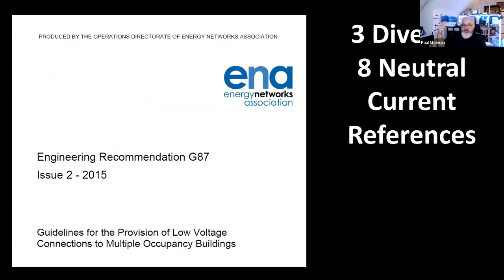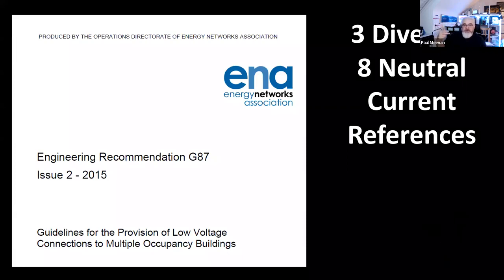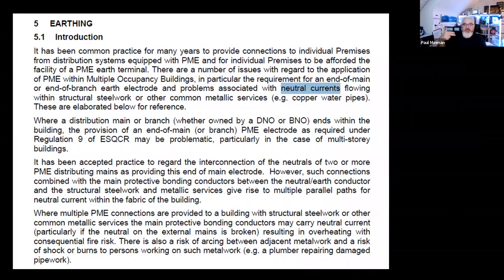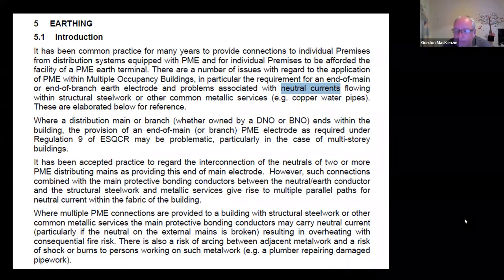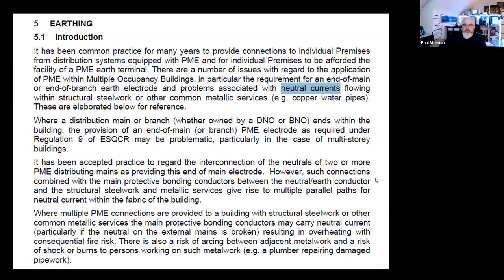Again, G87, 3 references to diverted neutral current and 8 references to neutral current diversion. And that's PME supplies to multiple occupancy buildings. It talks about, in general earthing, neutral currents flowing within structural steelwork, for DNOs, BNOs, and how we manage these high-rise buildings. A point worth making, Paul, the difference between G12.4 and G87 with multi-occupancy guidance is actually a recommended practice in G87, but there's not in 12.4, although the risk is the same of neutral current diversion. So one recognises it and has a recommended practice, but the other one doesn't.